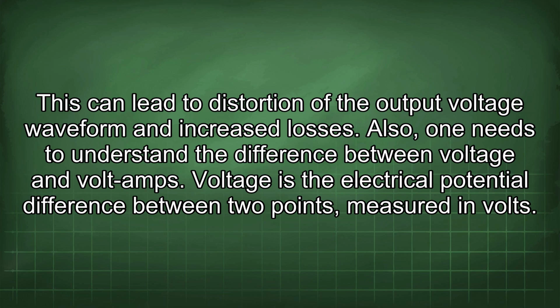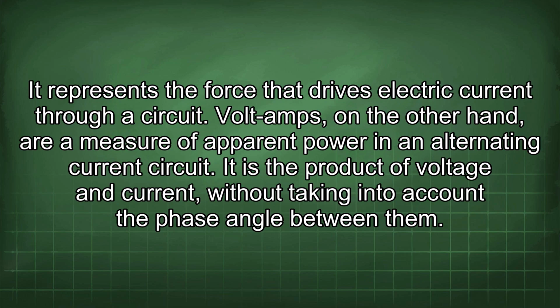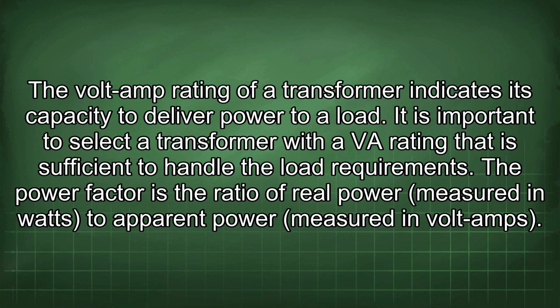Also, one needs to understand the difference between voltage and volt-amps. Voltage is the electrical potential difference between 2 points measured in volts. It represents the force that drives electric current through a circuit. Volt-amps, on the other hand, are a measure of apparent power in an alternating current circuit. It is the product of voltage and current without taking into account the phase angle between them. The volt-amp rating of a transformer indicates its capacity to deliver power to a load. It is important to select a transformer with a VA rating that is sufficient to handle the load requirements.